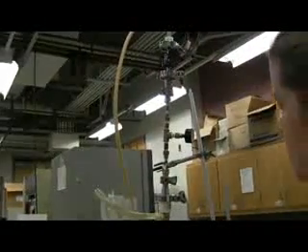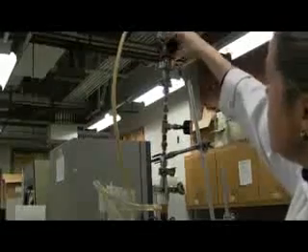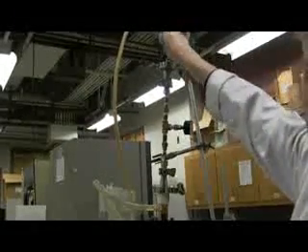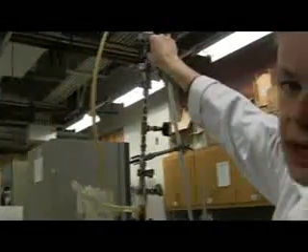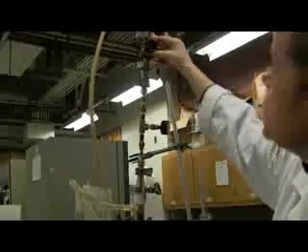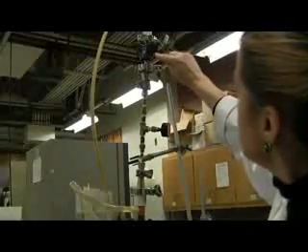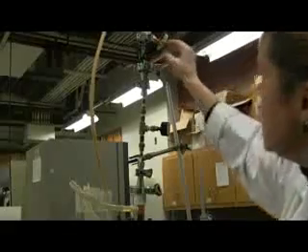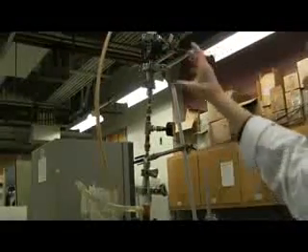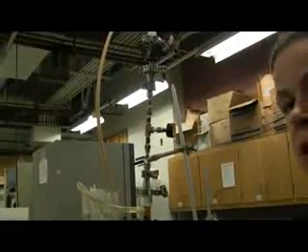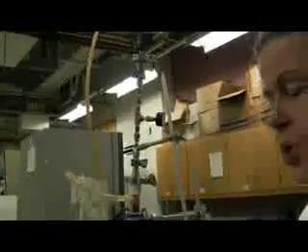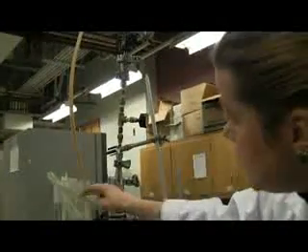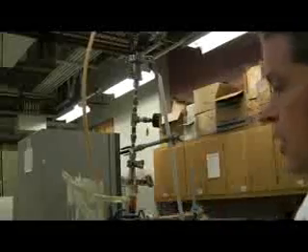So what do we use the valves for? When we start, we want to have this top valve all the way open, and you never have to remember righty-tighty, lefty-loosey, because there's an open arrow right there. So just turn it in that direction to open the valve. So you want to start with the valve open. What is that going to mean? The lowest possible back pressure, so the fluid flow through the permeate tube will be very little.